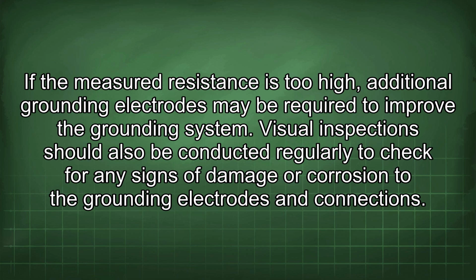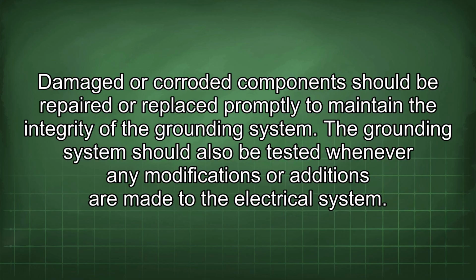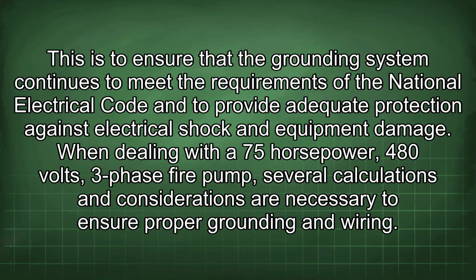Visual inspection should also be conducted regularly to check for any signs of damage or corrosion to the grounding electrodes and connections. Damaged or corroded components should be repaired or replaced promptly to maintain the integrity of the grounding system. The grounding system should also be tested whenever any modifications or additions are made to the electrical system. This is to ensure that the grounding system continues to meet the requirements of the National Electrical Code and to provide adequate protection against electrical shock and equipment damage.